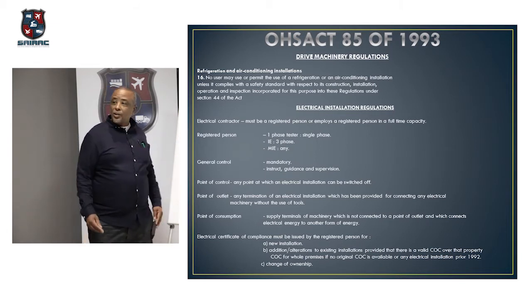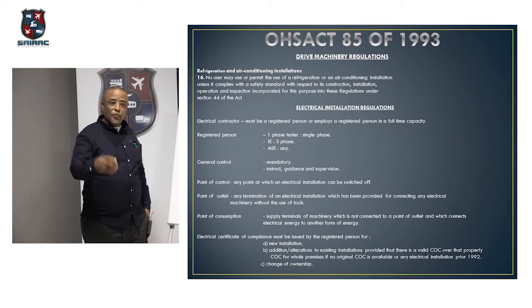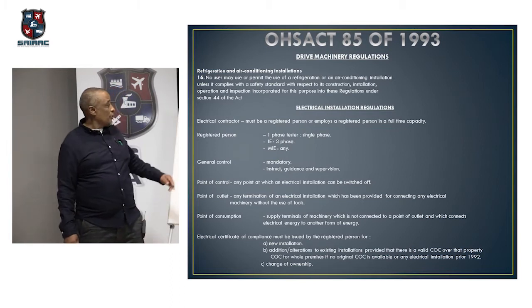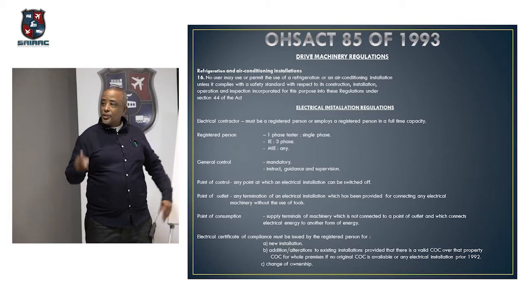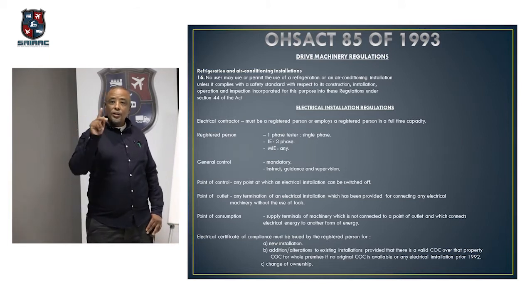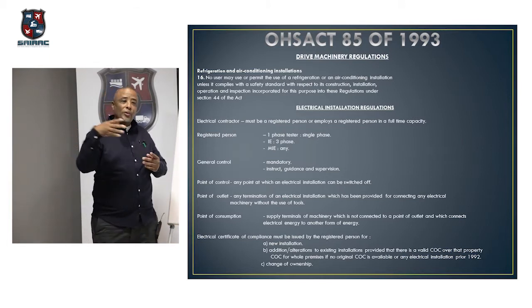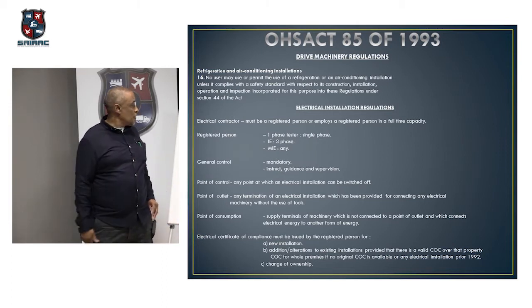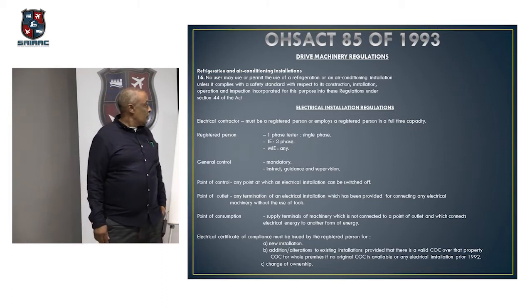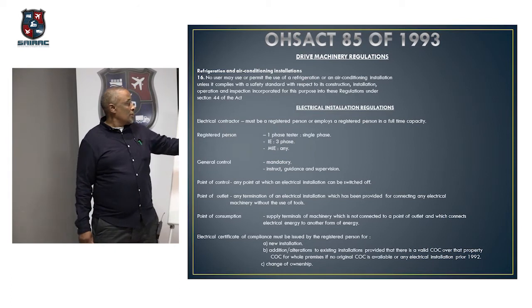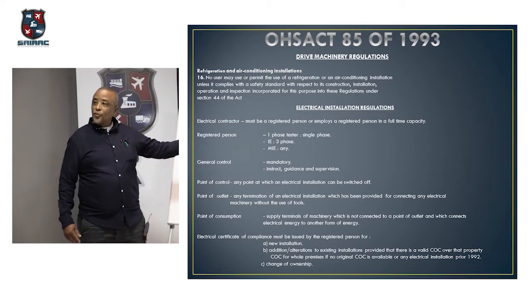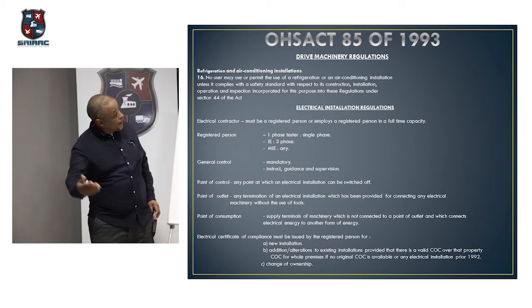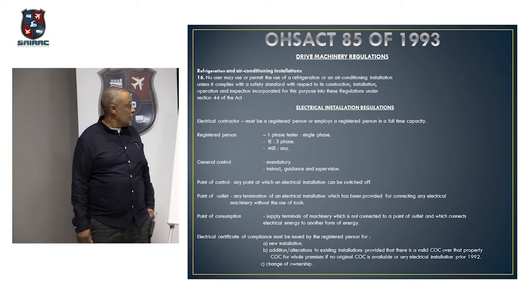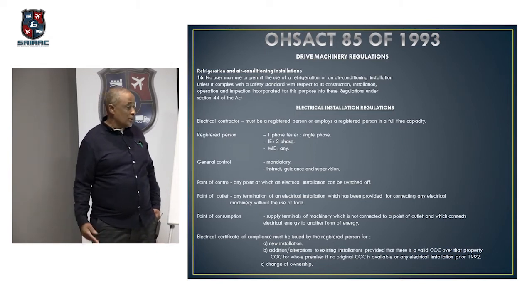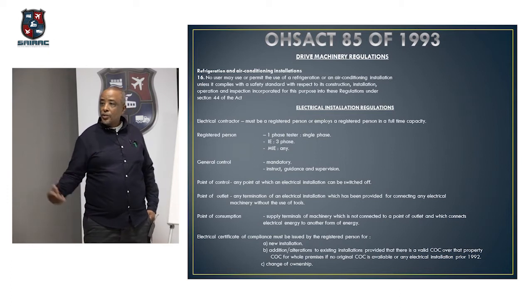Point of outlet, consider a socket outlet, whether it's a three-phase or single-phase socket outlet, that is your point of outlet. Point of consumption is the termination, maybe of your aircon, where you have your L1, L2, L3, that's your point of consumption. And that point of consumption supply terminals connects one form of energy into another form of energy, either cooling, heating, whatever.